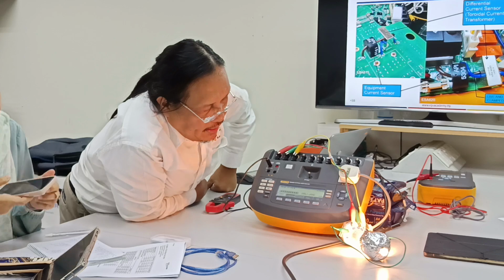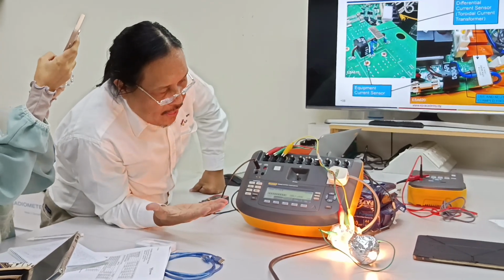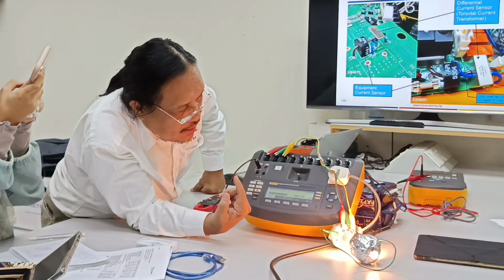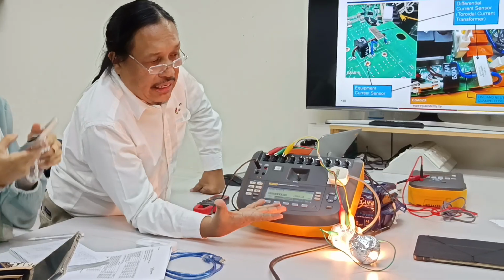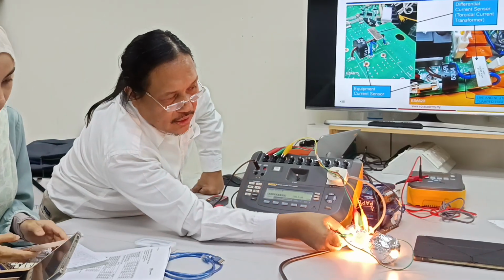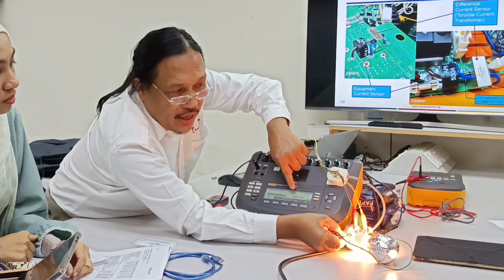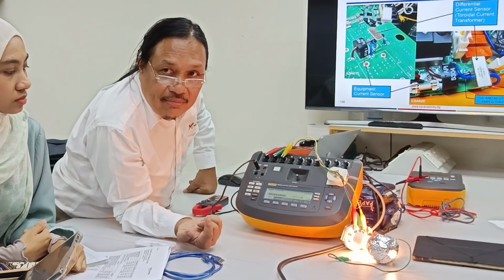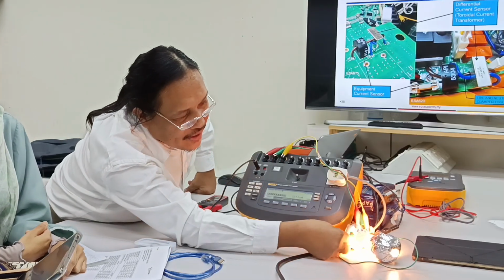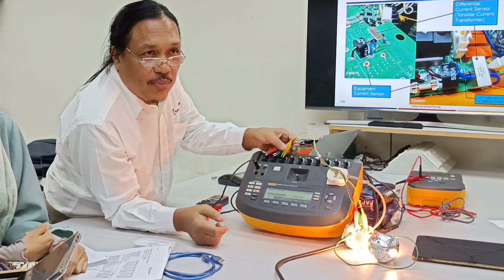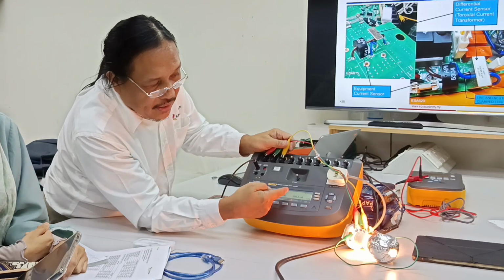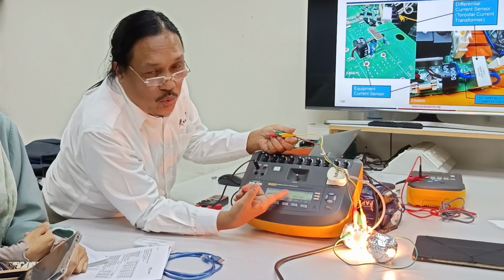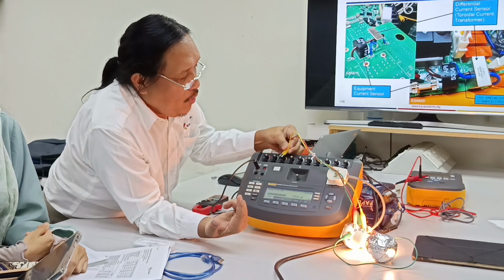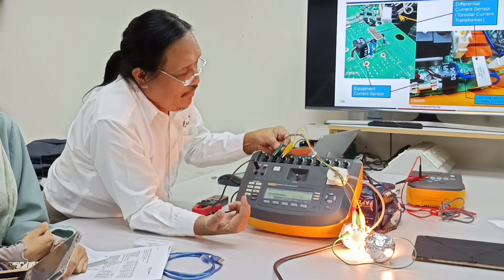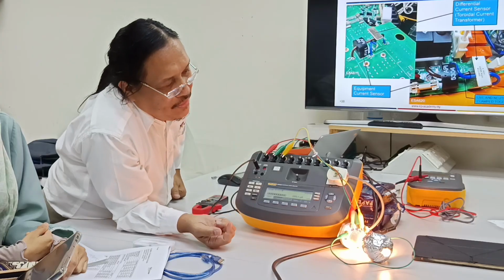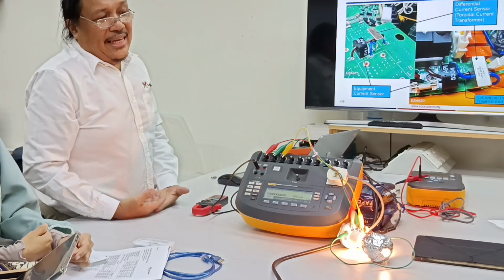So this is the leakage, 189, all combined leakage. This is AC only, so I'll select AC plus DC. See? It's easy to know whether this is really all the leakage. Try removing this. It will be lower, right, if you remove the non-earth? 137, because we removed one leakage, the non-earth. If you remove the applied part, you remove the patient leakage, so it will be lower. If you want to remove the earth leakage, remove the clip. So that's it: it's all the leakage combined, the 3 leakages.